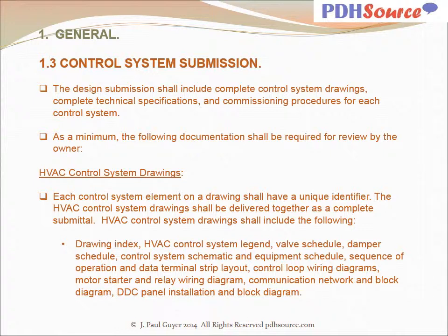HVAC control system drawings shall include the following: drawing index, HVAC control system legend, valve schedule, damper schedule, control system schematic and equipment schedule, sequence of operation and data terminal strip layout, control loop wiring diagrams, motor starter and relay wiring diagram, communication network and block diagram, DDC panel installation and block diagram.